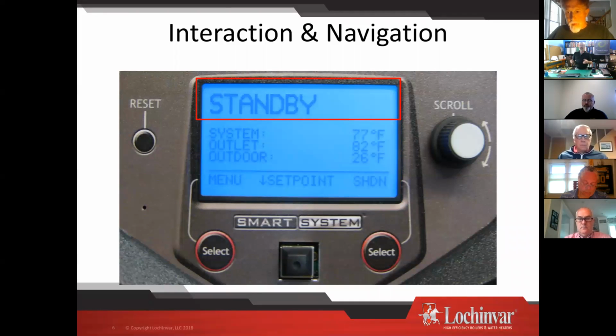What it's doing, that's going to be the top. Standby, start, ignition. It will show the boiler actually firing, shows a little flame, and what our firing rate is. That's all going to display across the top. To the right-hand side of it, when it's in operation, it'll let you know, do I have a heat demand or do I have a domestic hot water demand? That's going to show up right there.